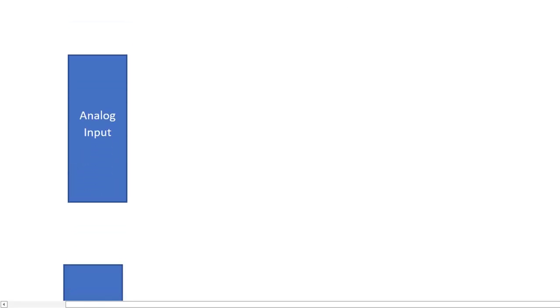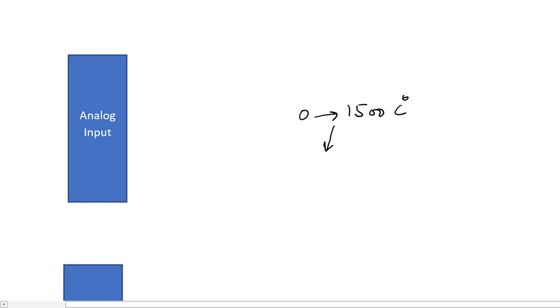Those sensors that send analog data to a PLC, for example temperature sensors that send data in a typical range, for example 0 to 1500 degree centigrade—that data is transformed to analog electrical signals, for example 4 to 20 milliampere. And these sensors are interfaced with analog input cards of a PLC.